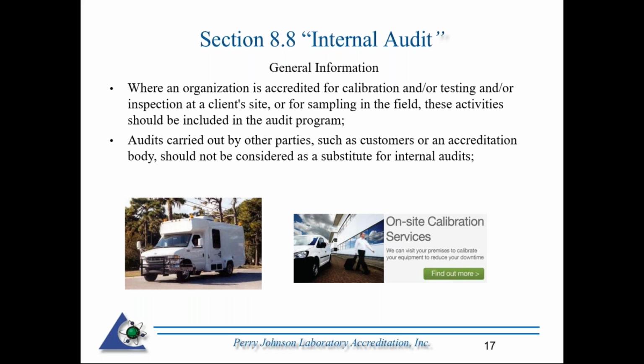the audit program. So if you're going to the customer site, I know quite a few of the calibration labs that I assess, they do calibrations at their fixed facility, and at the customer site, you want to audit the testing or calibration where they're being undertaken. So if they're being undertaken at the customer site, you want to assure that, i.e., is the equipment being maintained, set up properly? Are the environmental conditions being recorded off-site? And if they are out of tolerance, as stated within the procedure, then are your personnel handling that appropriately? And that's specified in 17025, what to do under those specific circumstances.